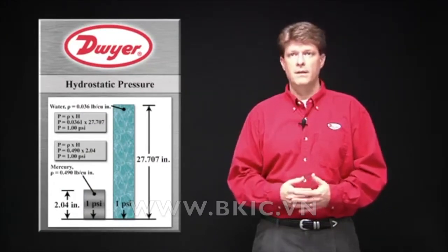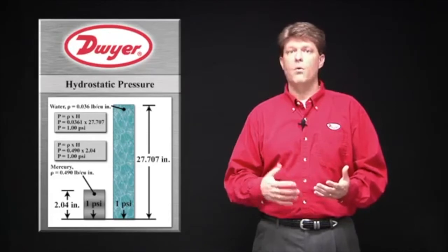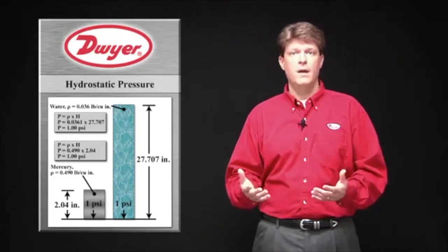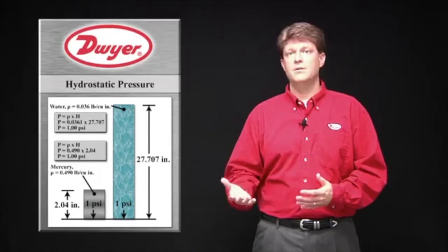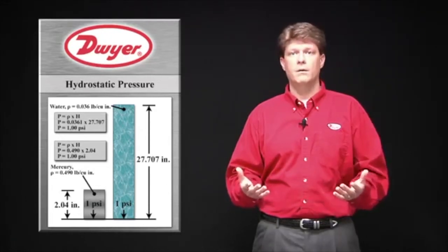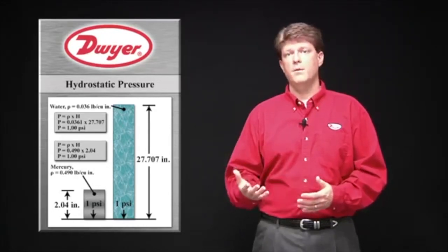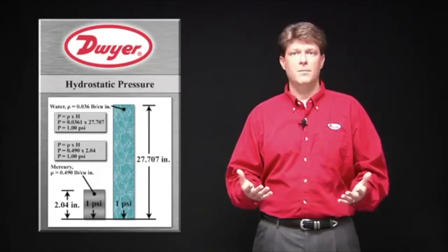Hydrostatic pressure is the pressure created by the hydrostatic force per unit area at the base of a column of liquid. This can also be called the pressure head or head pressure, and is often referred to as the height of the fluid, such as inches of water column, inches of mercury, or feet of water. The measurement is dependent on the liquid density and independent of the shape of the container, based on the property that pressure equals density times the height of the liquid.